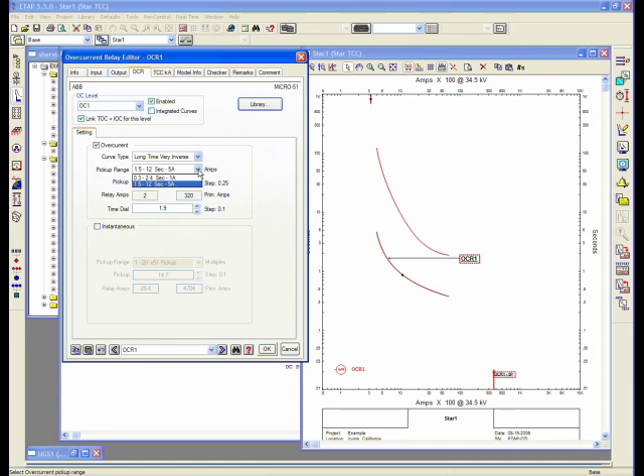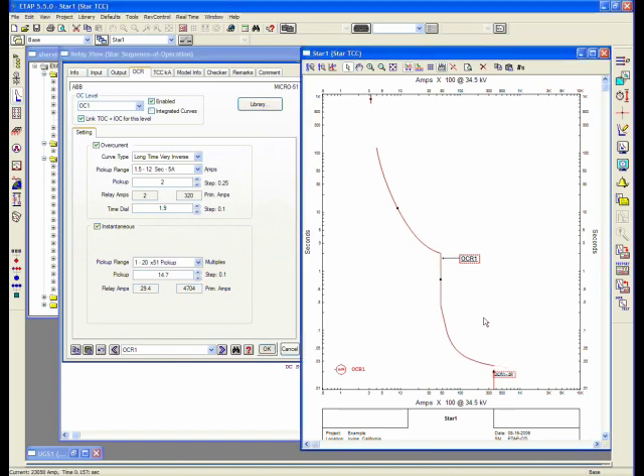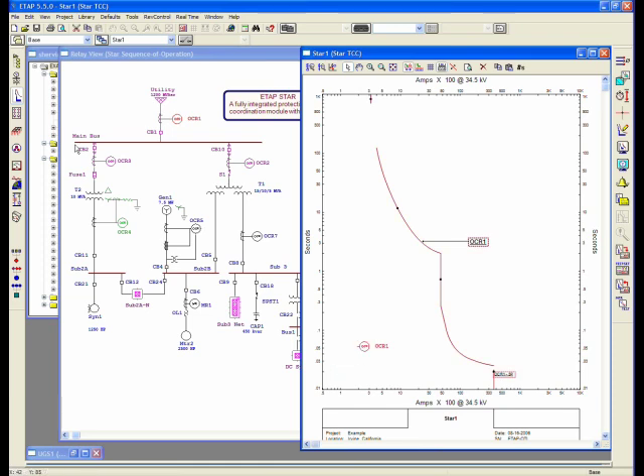There's a 1-amp model, which is used typically in the European market, or IEC, and the 5-amp, which is typically used in North America. You can change the settings and time dials directly from here. If you want to enable the instantaneous device, you can turn on the instantaneous and change the pickup range and the pickup settings, and you would get a new curve as shown below. The element interconnection or the interface between star and ETAP, a one-line diagram, is basically such that you could bring the elements into your new stars or existing stars and display them.